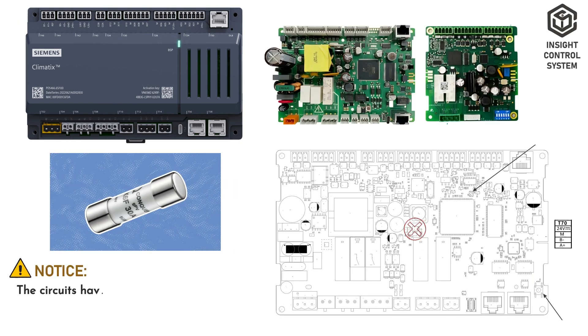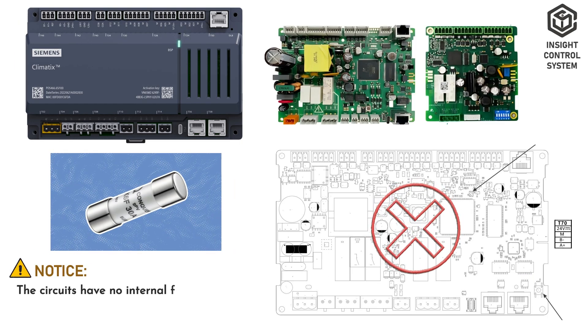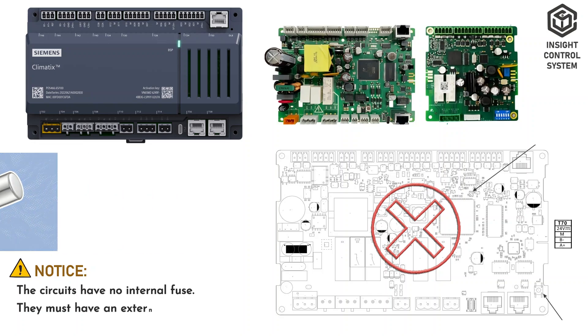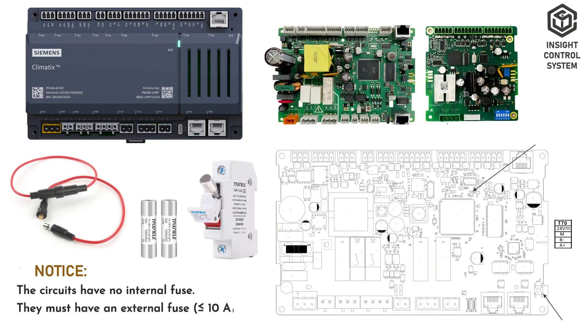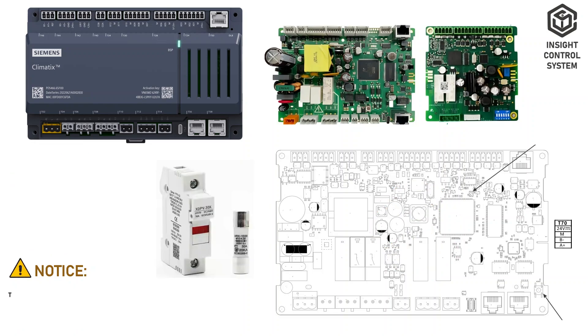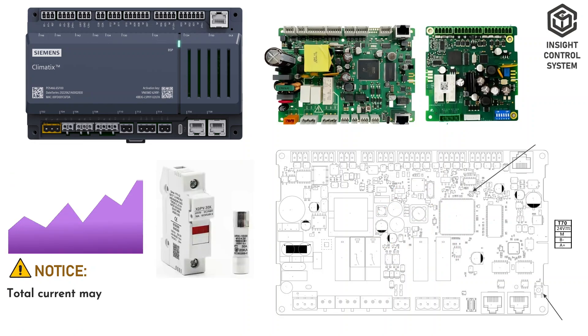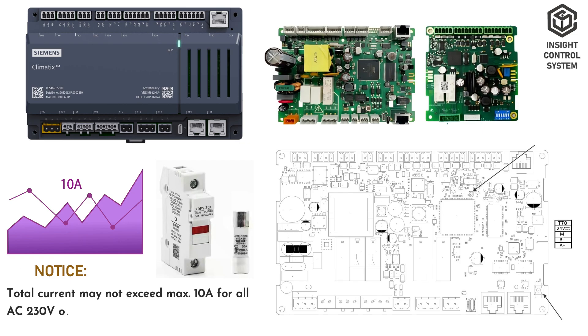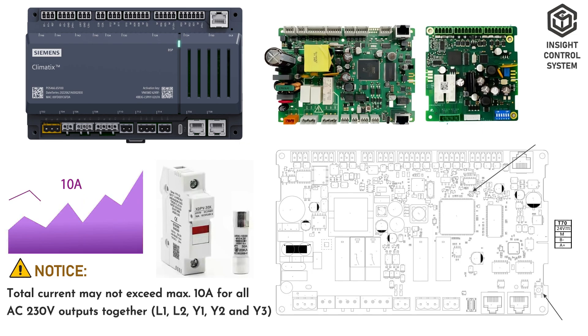Note: The controller circuits have no internal fuse. They must have an external fuse of less than 10 amps. Total current may not exceed a maximum of 10 amps for all AC 230 volt outputs together.